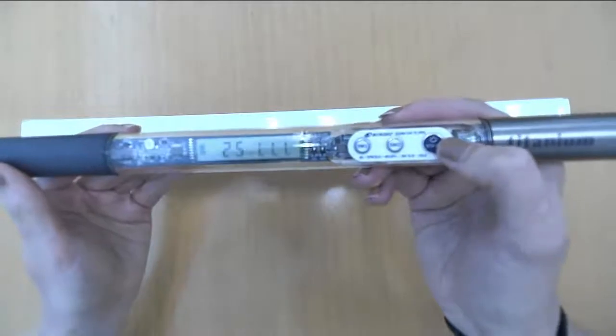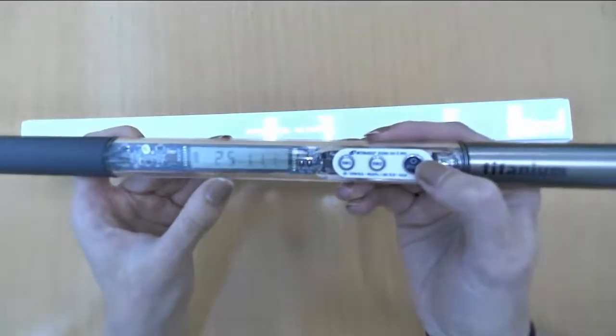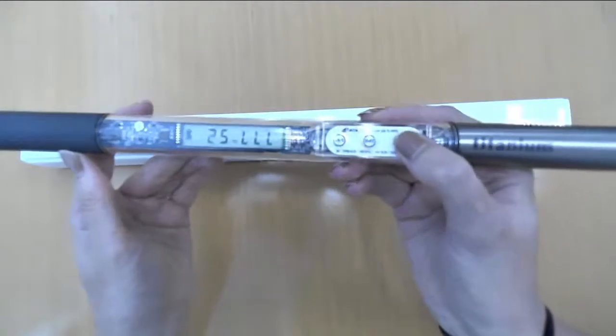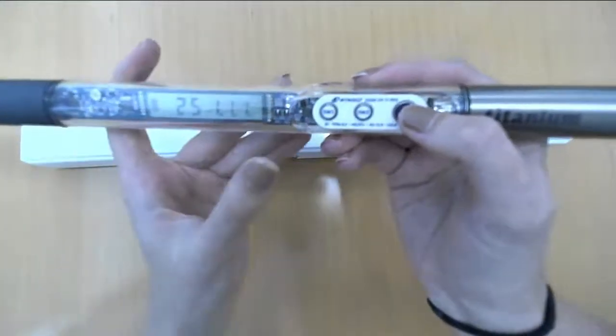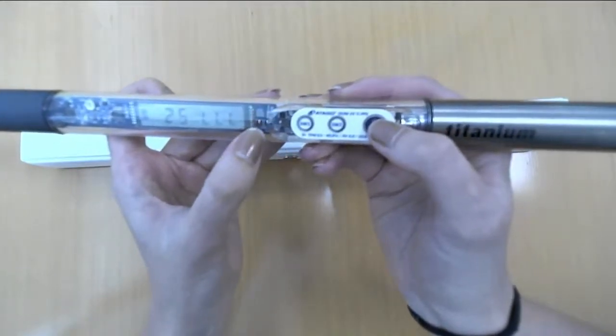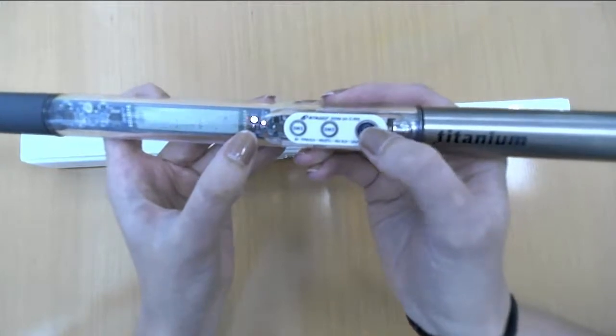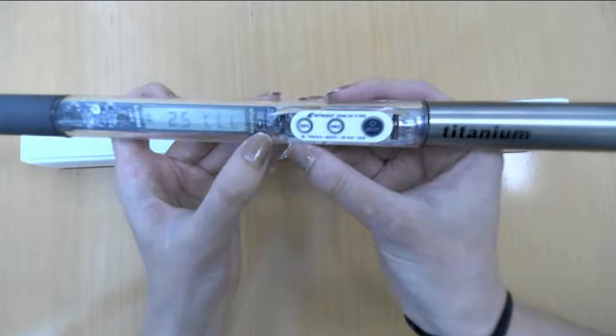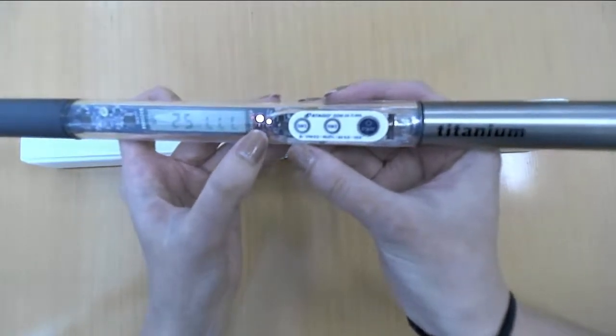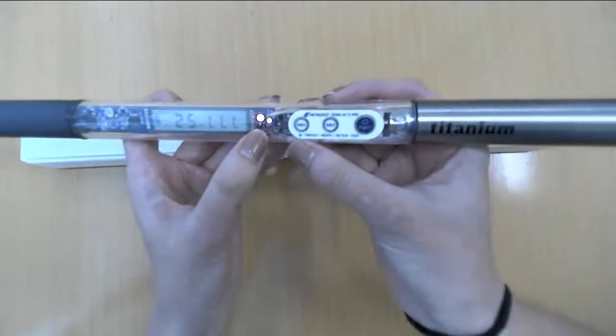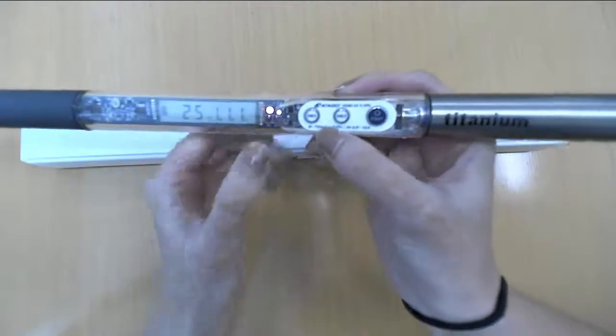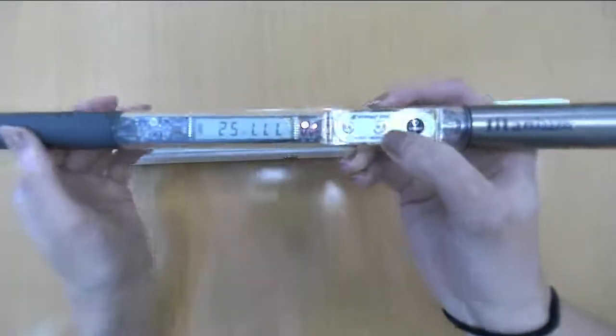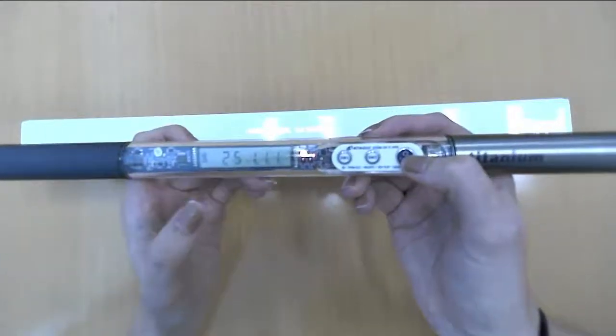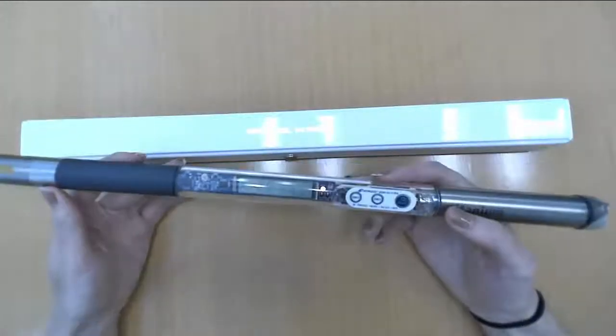So once it's on, we just press start, and then it will begin measuring. So here we'll see the temperature as 25 degrees C, and then it's blinking LLL because I don't have it in anything right now. And then if I can get it out the right way, I hope you can see the blinking light over here. So it's blinking red right now because it's desperately trying to measure, but it can't because there's no sample. So it's saying that it's unstable and not ready for the measurement. But if it were measuring oil, then once it reaches its measured value, this light will turn green. So right now it's red because it failed at measuring because there's nothing, but once there's sample, it will turn green. And you will see that in the video that I am about to show you.